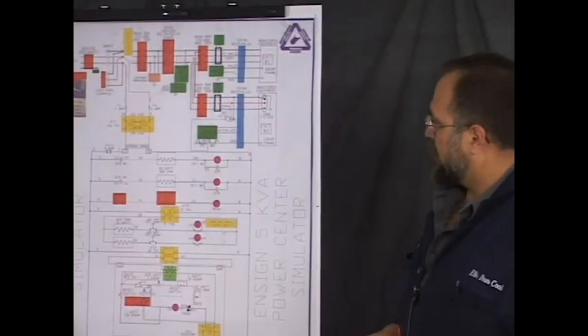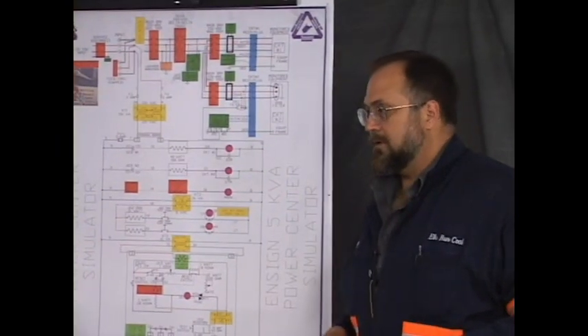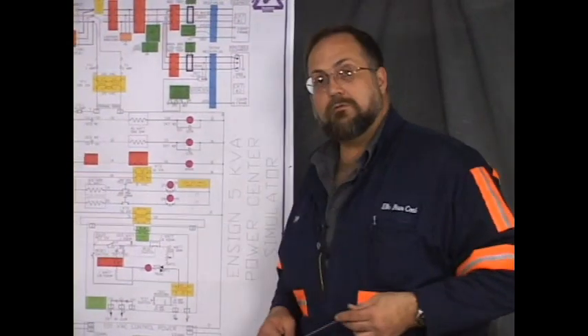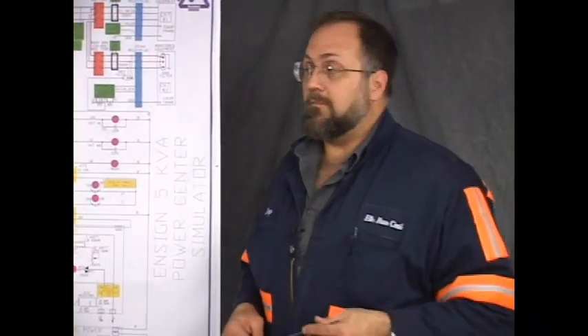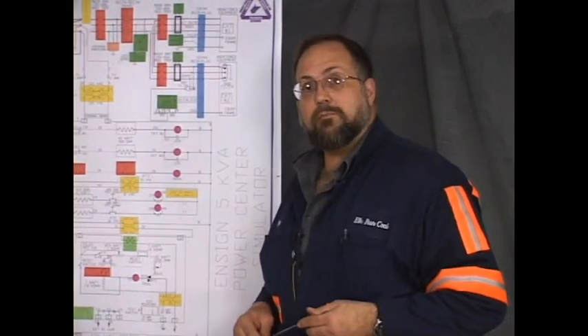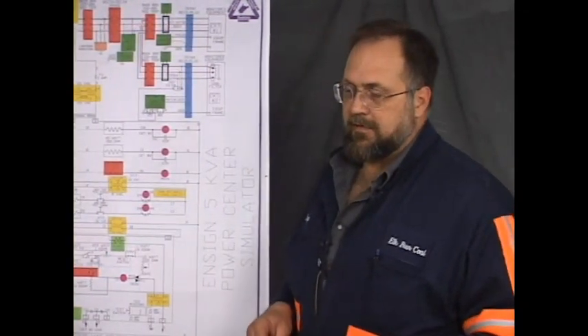Current transformer responds to a magnetic field, a flux that surrounds an energized conductor. Now, to induce, you have to have 3 elements. You have to have a magnetic field, a coil, and the CT is a coil. You have to have relative motion. Now, these wires are obviously not going to move, but we have 60 cycle power. In 60 cycle power, if you should view a sine wave, the current flows upward. It's changing constantly in magnitude, and it peaks and then it goes down to neutral, and then to a corresponding point, an equal point below neutral, and then back up. That's one cycle. And it does this 60 times a second.